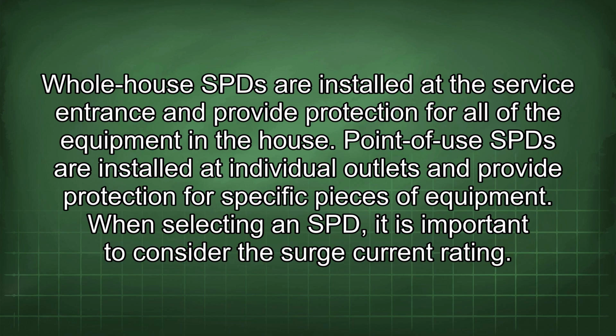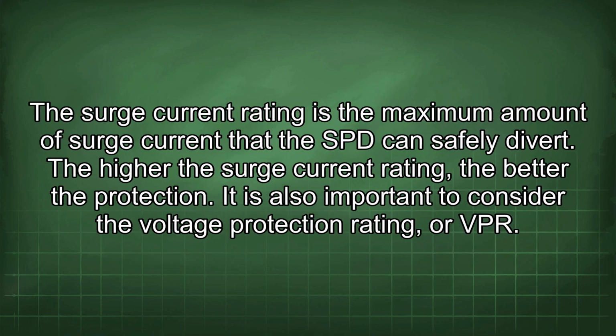When selecting an SPD, it is important to consider the surge current rating. The surge current rating is the maximum amount of surge current that the SPD can safely divert. The higher the surge current rating, the better the protection. It is also important to consider the voltage protection rating, or VPR.